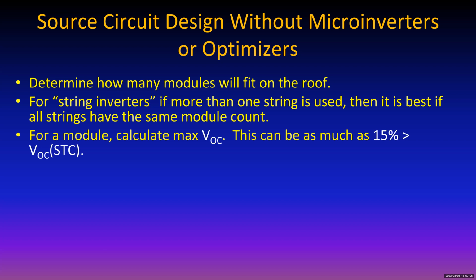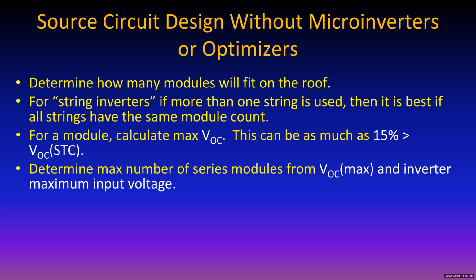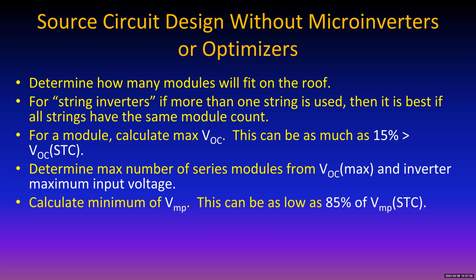Then calculate the maximum open circuit voltage. You don't have to do this with the microinverters or the optimizers, but here you need to do it because you need to make sure you don't damage your inverter by having the string voltage go too high on that cold winter morning and actually damage the electronics in the inverter, where it's only capable of handling, say, 600 volts max or 1,000 volts max or 1,500, whatever the case may be, depending on the size of the system. Okay, so then determine the maximum number of series modules based on the open circuit maximum voltage at the coldest temperature and the maximum rated input voltage for the inverter, which if it's a house, it's probably going to be 600 volts. Calculate the minimum of the maximum power voltage.